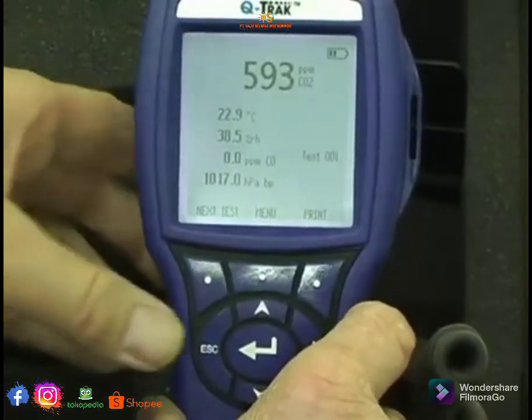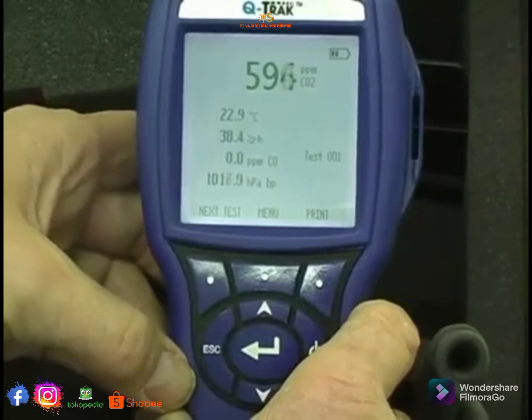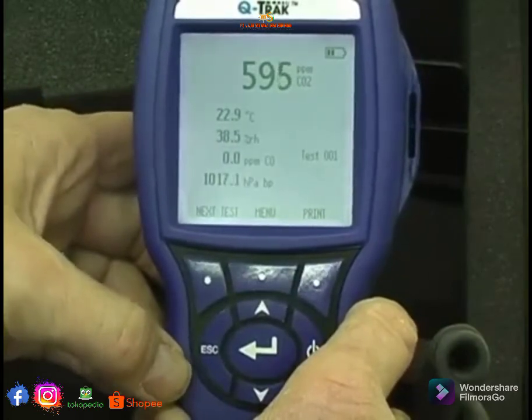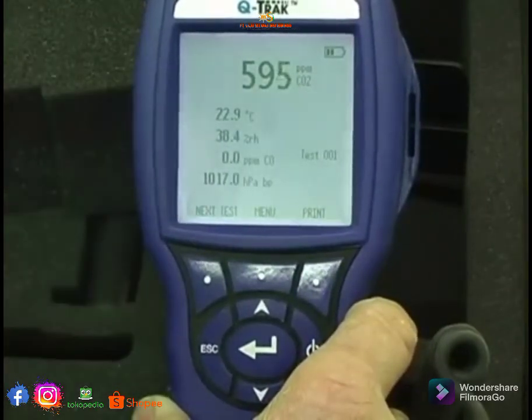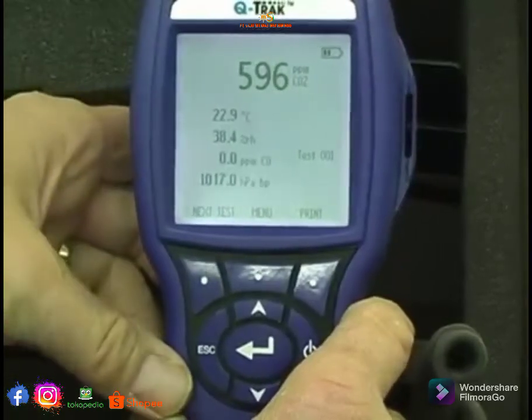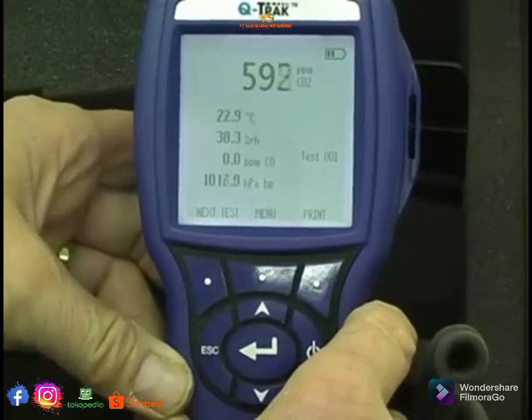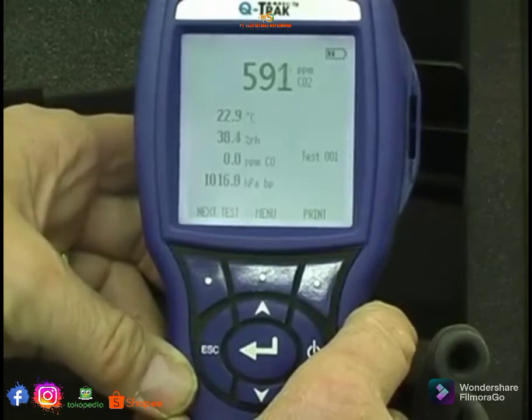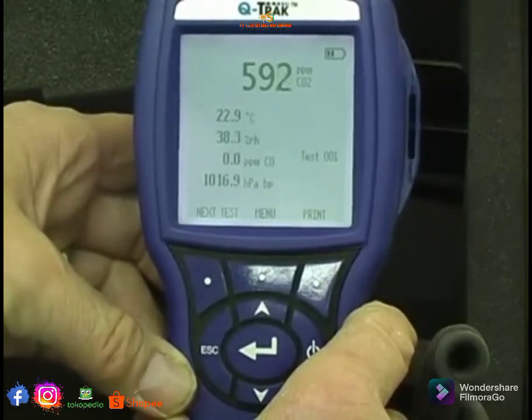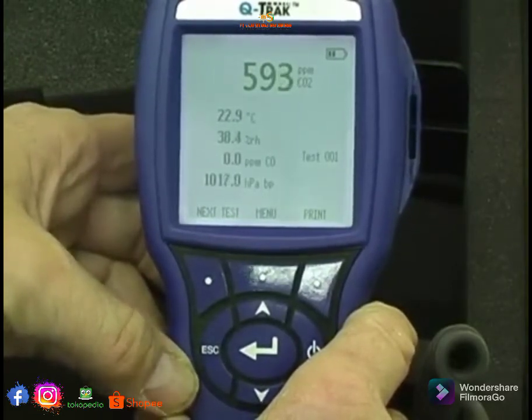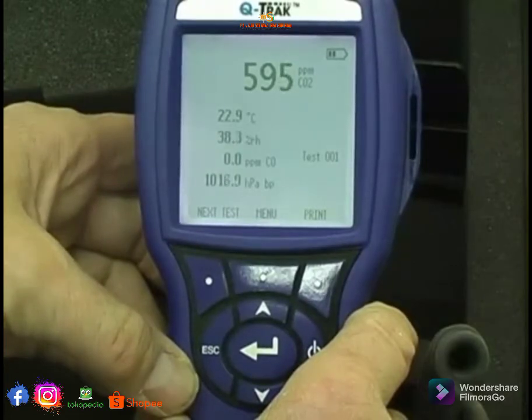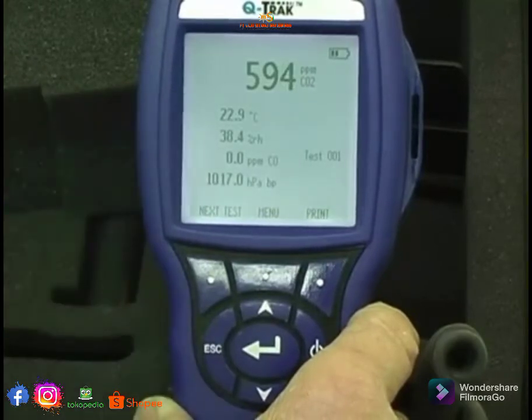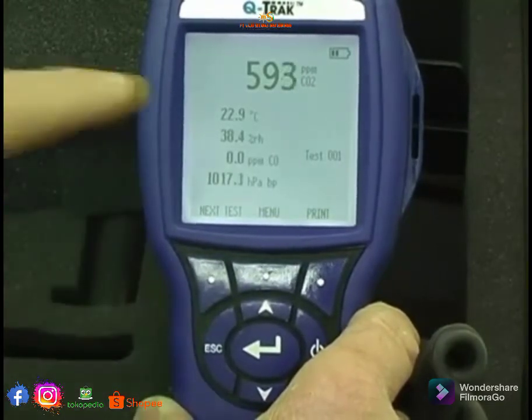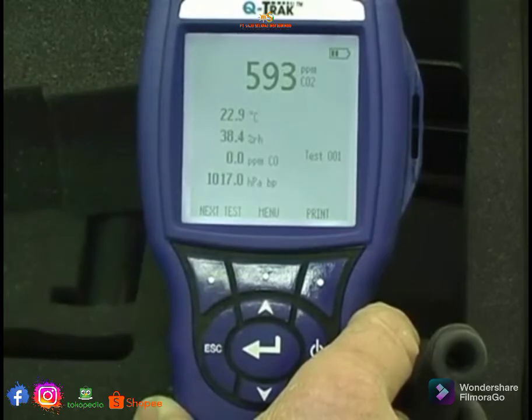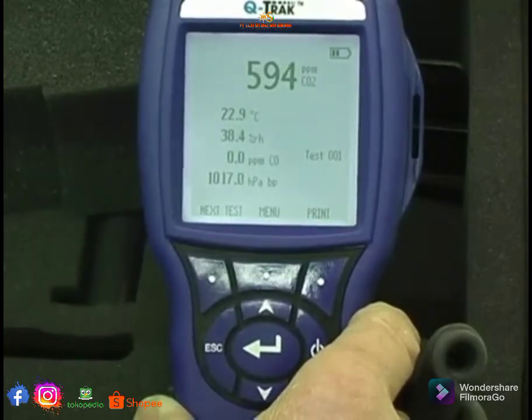Now the CO2 level at 593 is reasonably acceptable inside an office environment. Now if CO2 levels get to 1000, I'll start feeling quite sleepy, and if they get to 1200 I'll be yawning and really needing a coffee. So it's a very useful measure for determining air quality. So we'll just go through setting up data logging with this, because if I stand too close to it I'll get a much higher CO2 measurement because my breathing will cause that.